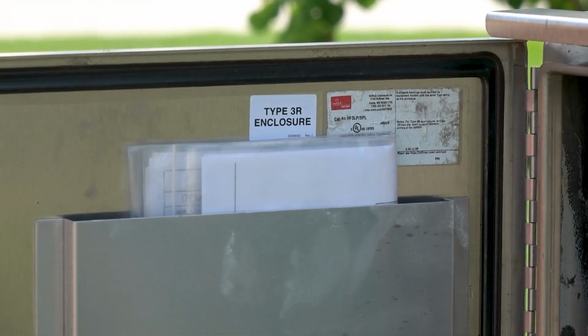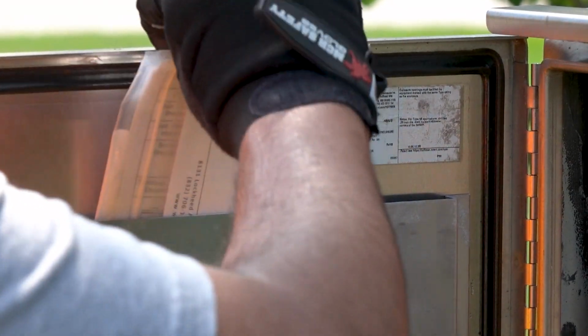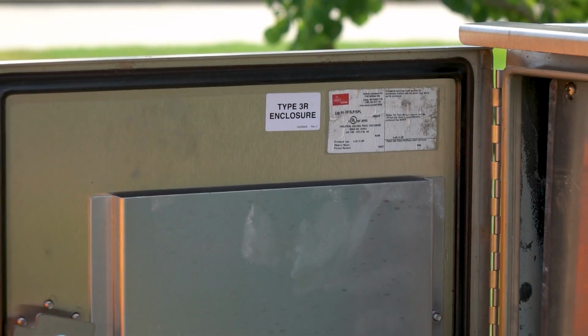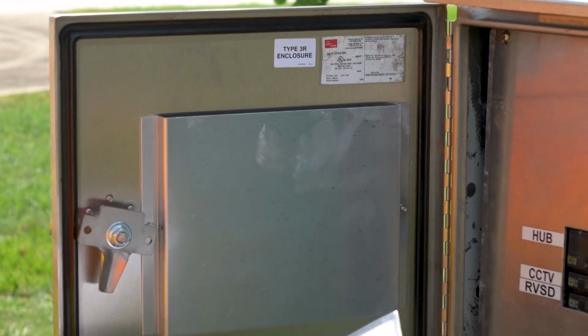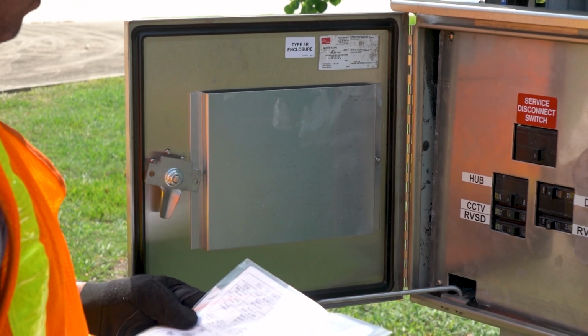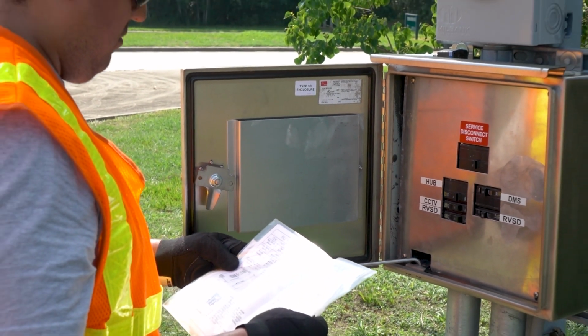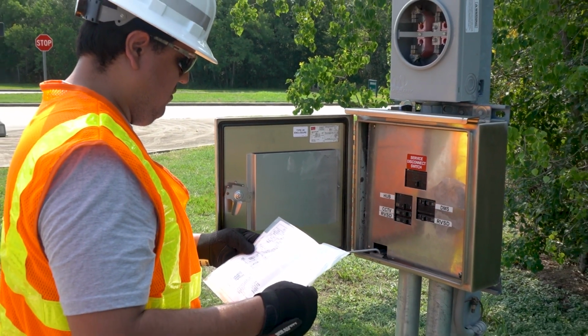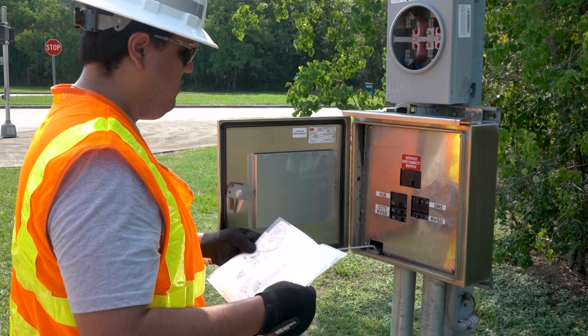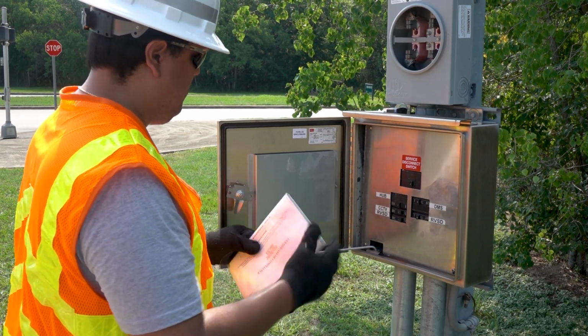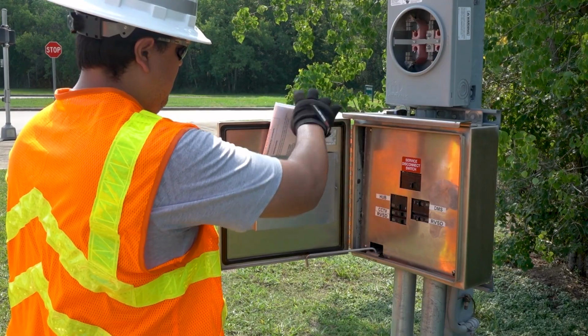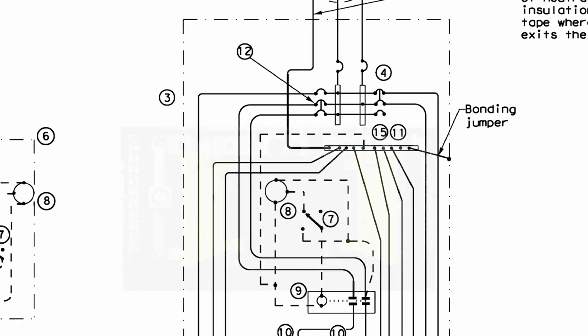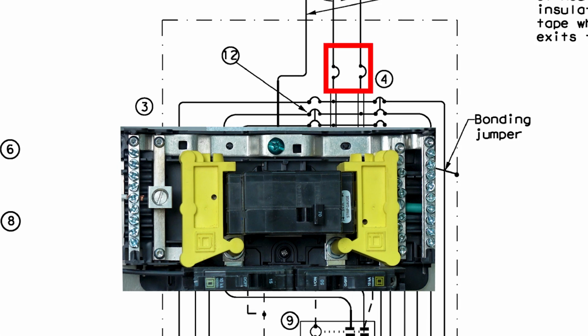In the enclosure data pocket, the inspector should find laminated panel component layout sheets provided by the UL 508 shop. The inspector should locate the main circuit breaker on the laminated drawing and compare the ampere rating to what the plans call for on the electrical service data chart for that service. The legend on standard sheet ED6 identifies the main disconnect breaker with the number 4.